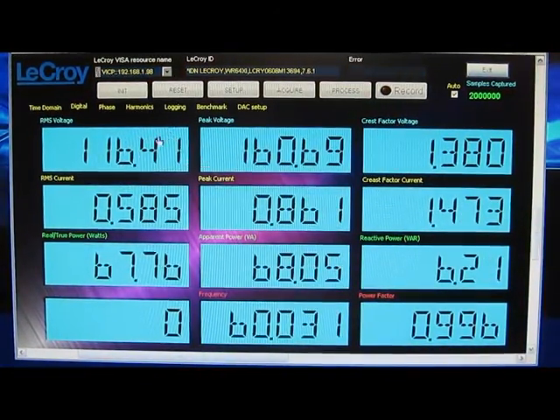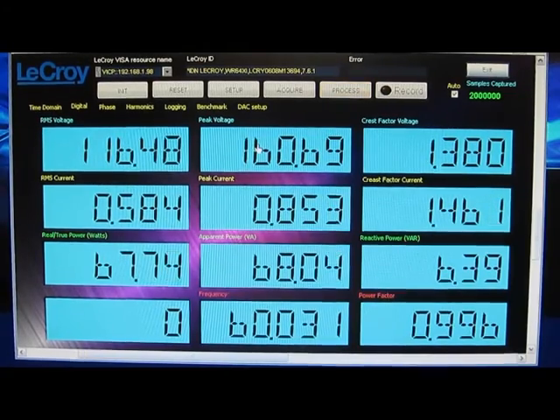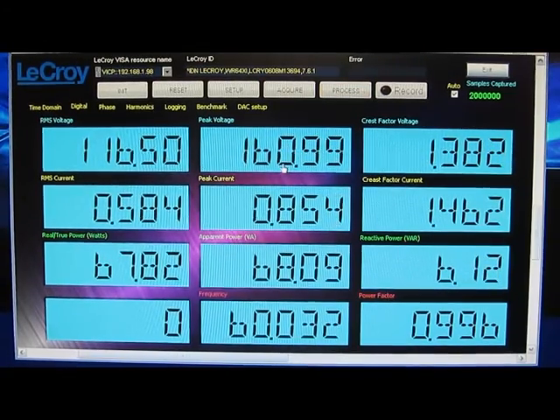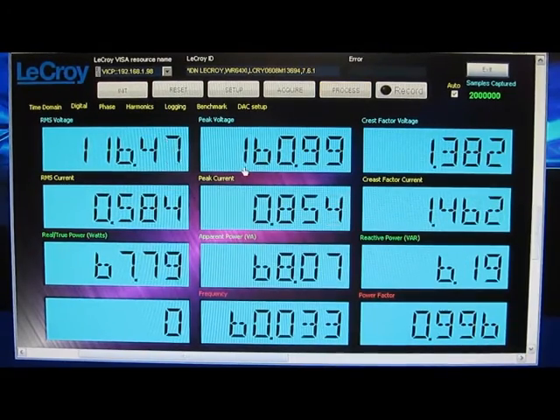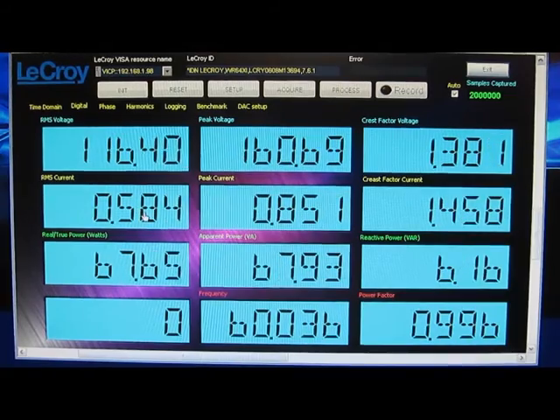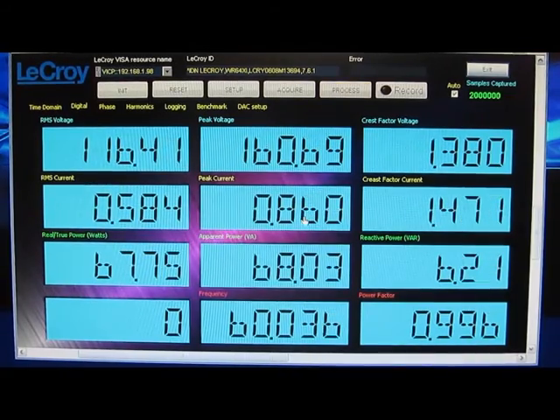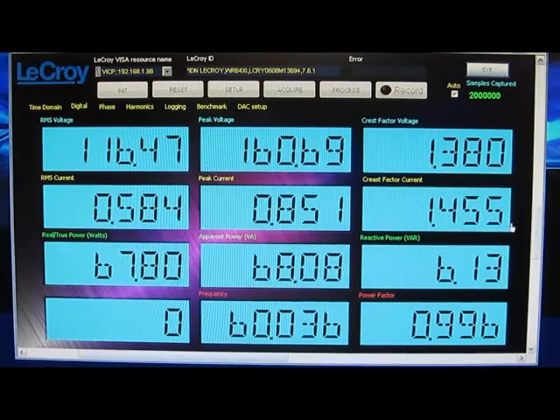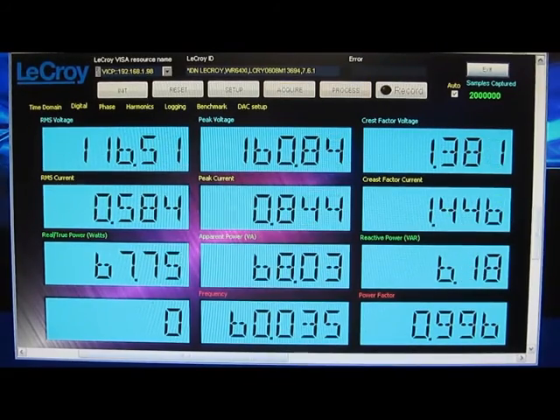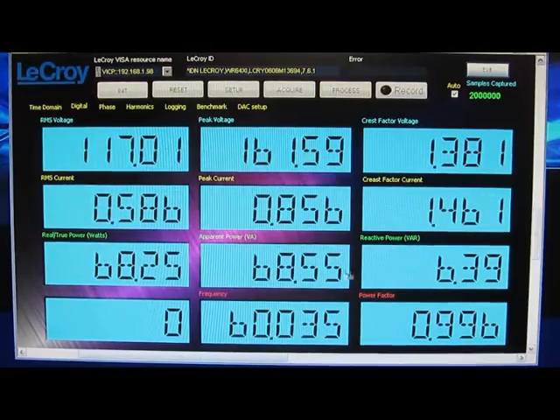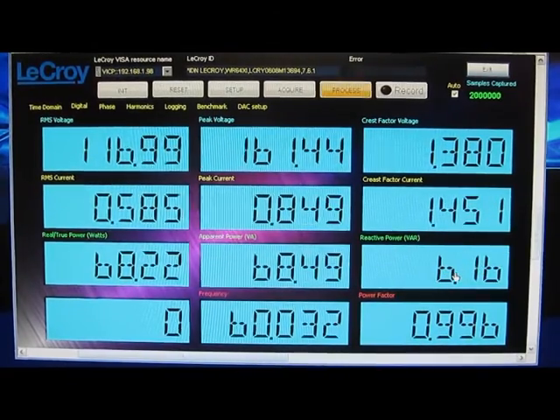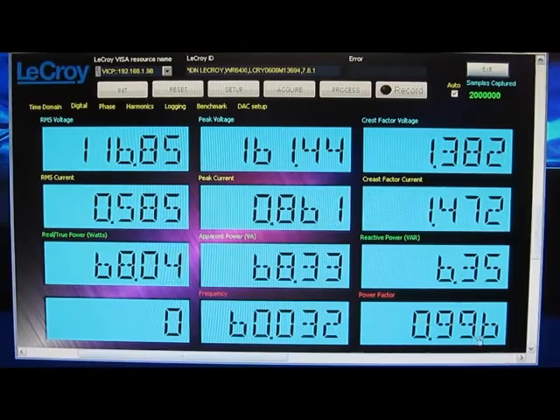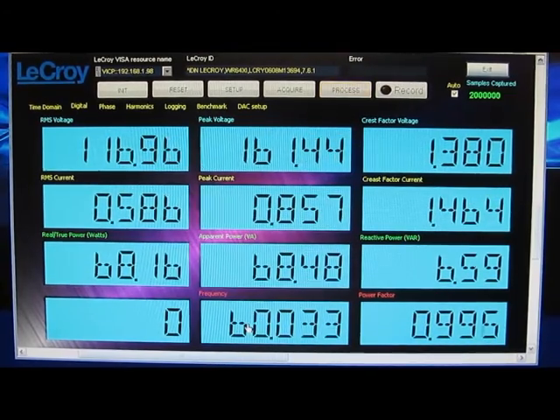This is looking at the line voltage again. So we can see it's 116 volts coming in, or 160 volts peak. Crest factor is 1.38. RMS current about 0.6 amps. Peak current about 0.8. Crest factor for the current is 1.4. Roughly 68 watts, and our reactive power again quite low. Power factor is roughly 1. We'd expect that for our resistive bulb.